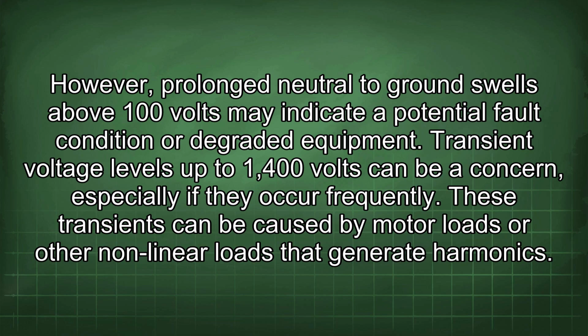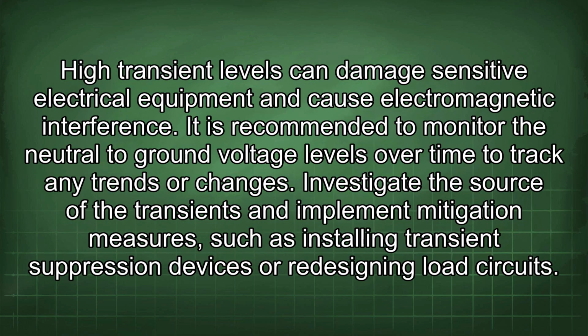Transient voltage levels up to 1400 volts can be a concern, especially if they occur frequently. These transients can be caused by motor loads or other non-linear loads that generate harmonics. High transient levels can damage sensitive electrical equipment and cause electromagnetic interference.